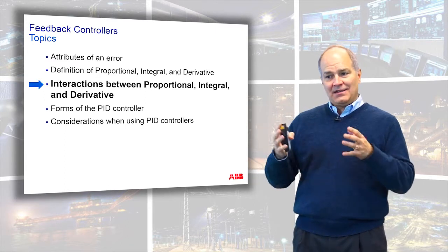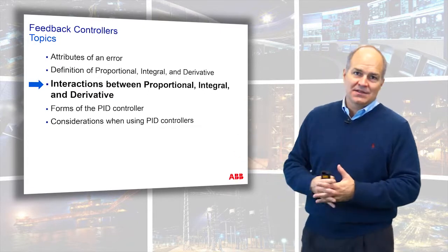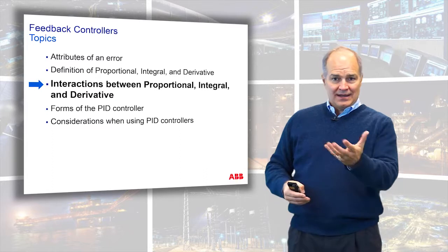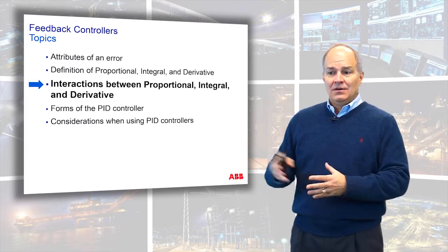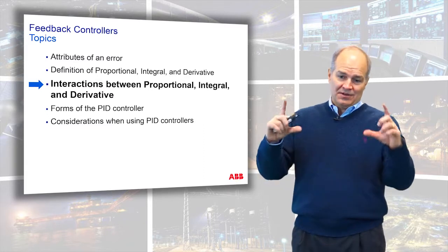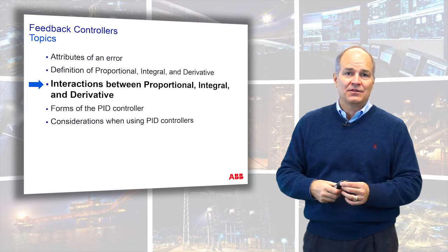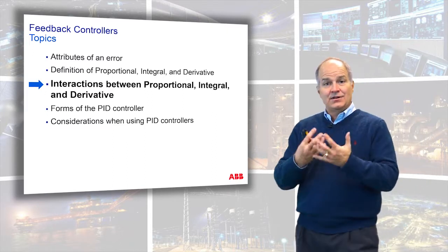So if you understand the concepts that we've covered so far, then going into tuning will not be such a big deal. And I've used this to troubleshoot. If you walk up and you can look at the dynamics of the process and you can see what the output's doing, you can say, ooh, that's not right. Or if you don't know what the controller is, you can make a generic controller or you can put up a bench test, you can tell how the tuning interact. That covers PI and D interactions.